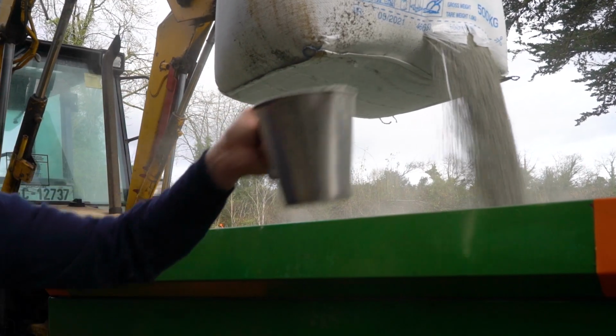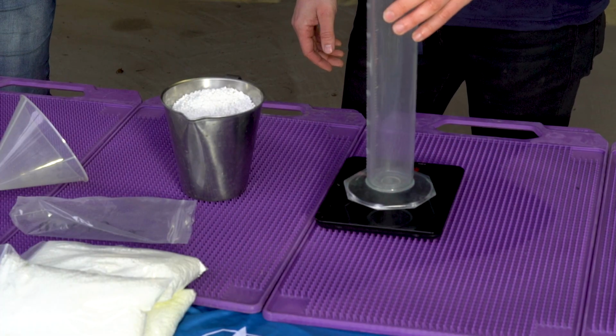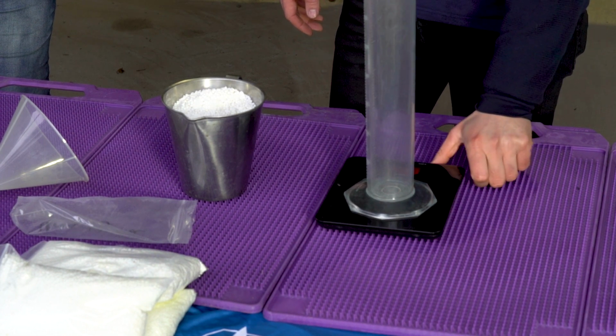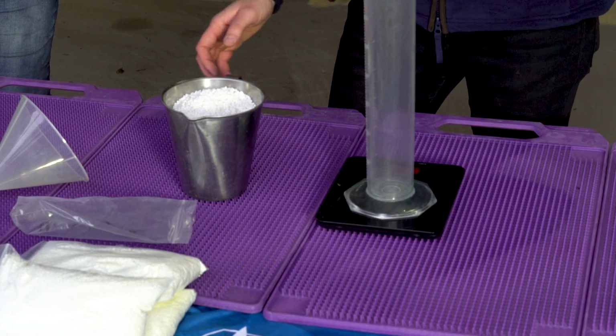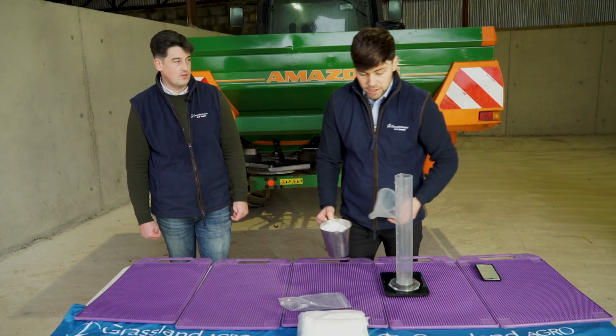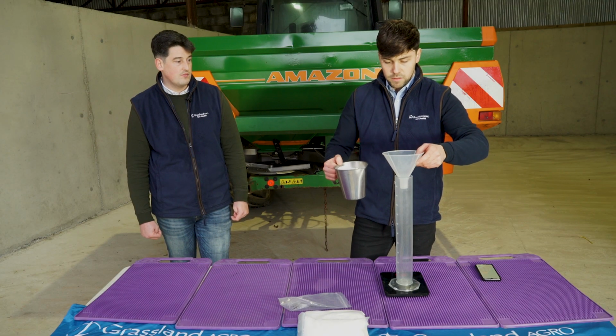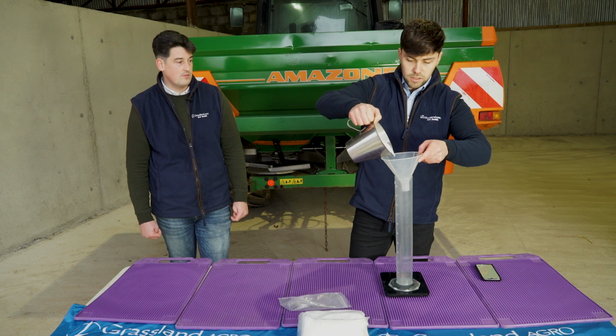Any instrument that can accurately measure 1 litre works. I'm using digital scales, so I can use the scales to tare the weight, which subtracts the weight of my measuring device. If you're doing this manually, just take a note of the weight of the cylinder and subtract this at the end. So then I pour in my sample.